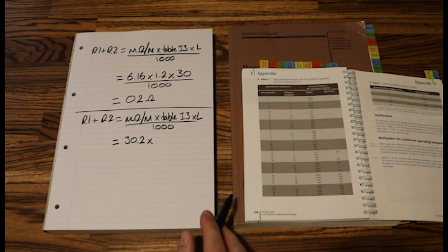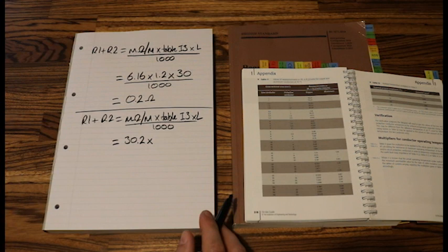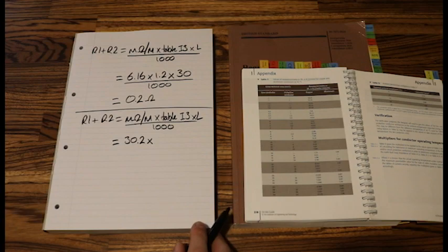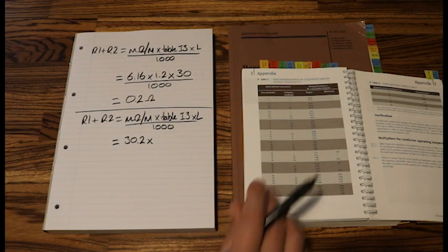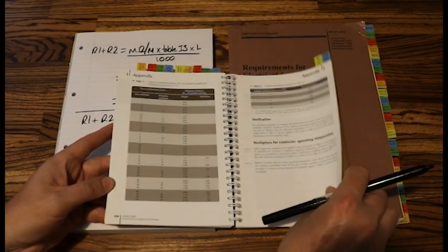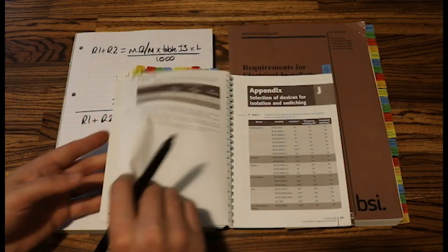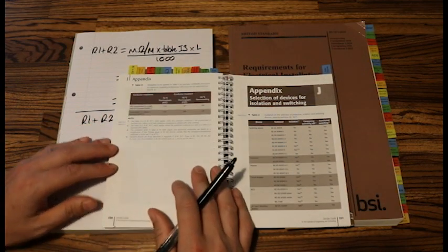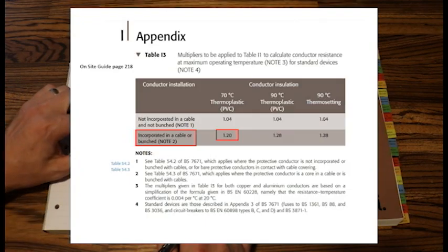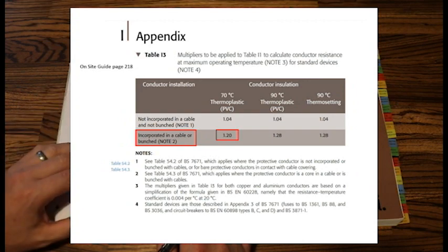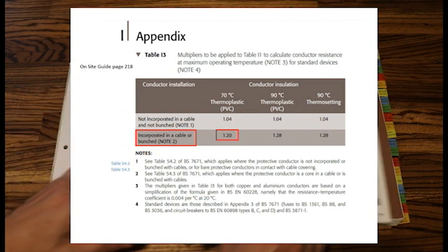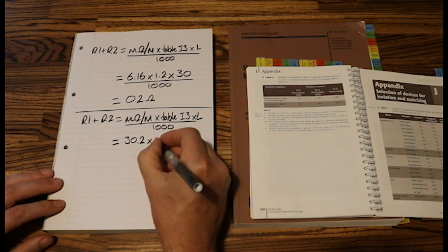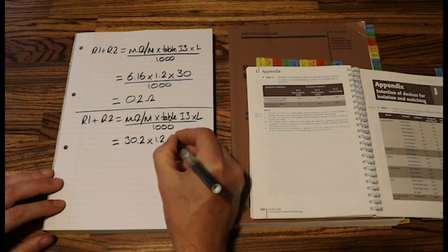This question is not run with any other circuits, but mineral insulated is a multicore cable. So again, table I3 factor, our conductor is incorporated within a cable. So again, I3 value is 1.2.